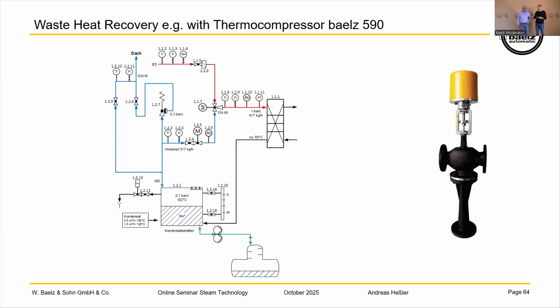It can be used if you have low steam pressure or a high steam pressure loss going through your heat exchanger. But normally using pumps. Yeah. Normally, because you have to pay a lot of money for steam, and you don't want to use it just to put your condensate back to the pressure. You use condensate pumps. They're much cheaper. Basically, in most BAELZ applications, I would say they are not necessary. And when we need it, we're using pumps. Yeah. All right. Perfect.